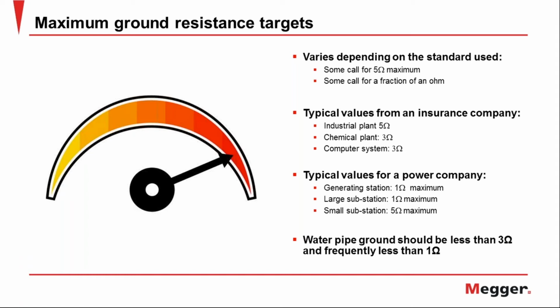And we begin with, okay, we're going to do a ground resistance measurement. That's going to give us a number. So what? Well, in the US, and I'm sure a lot of you have already heard this, 25 ohms or less, that's the only prevailing code that goes across the whole nation. And that's from the National Electric Code, but it's very forgiving, and the code itself will tell you that.